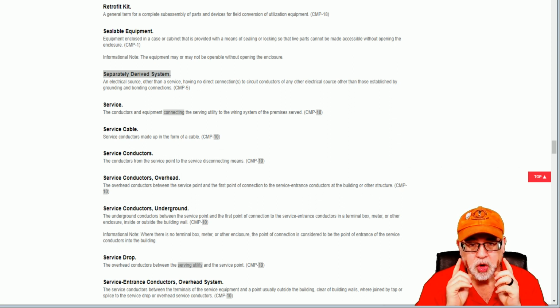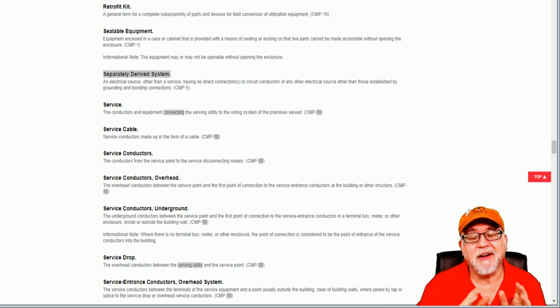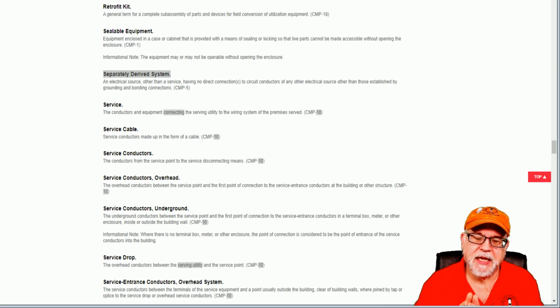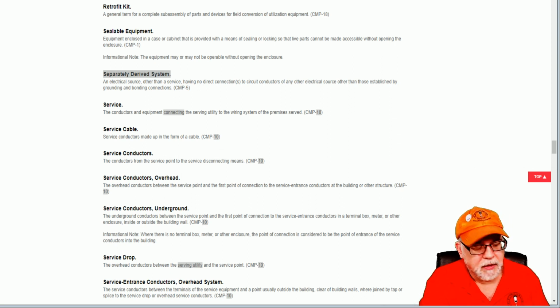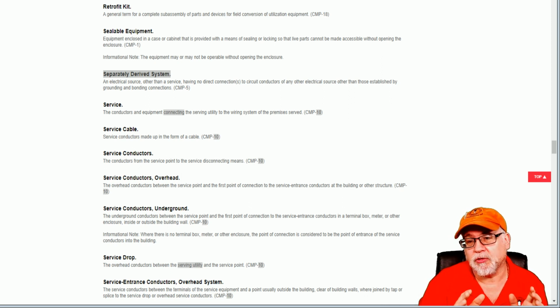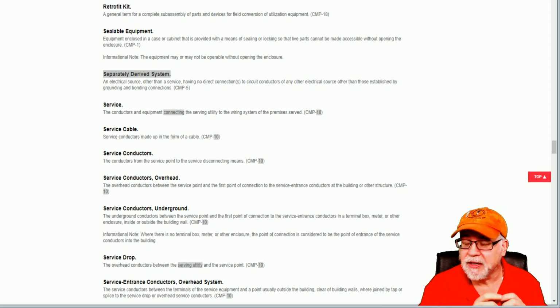which reminds me, if you want to learn about transformers and the code and secondary conductors and things like that, we have a 6-part video series free over on our channel. Just go over to youtube.com/Master the NEC channel, go to the playlists, and you will find our transformer videos. They were put out over a year ago, so you'll have to search for them, unless you go to the playlist, then you can find them. Watch each one of them, because we build on it from piece to piece. That's important, because you need to understand how to take the values of a transformer and find out what the amps are so that we can apply it for conductor sizing and overcurrent protection of the transformer. All of that's critical steps that you have to follow. So it's a great series. Go check it out over on our website.